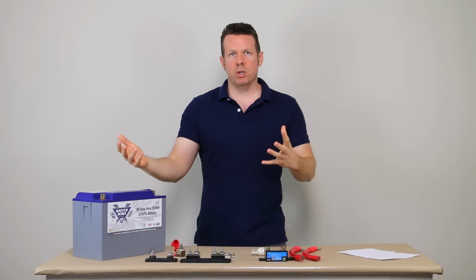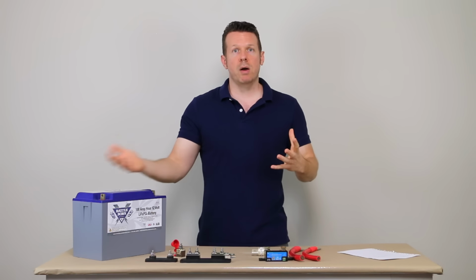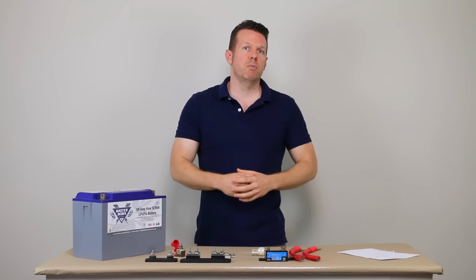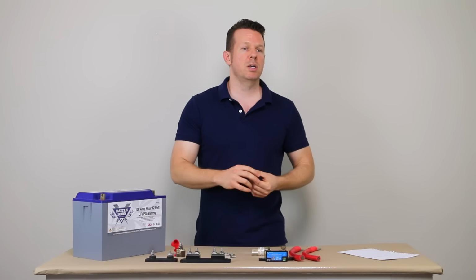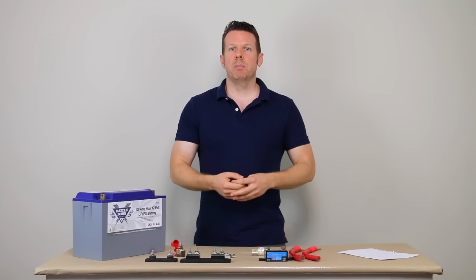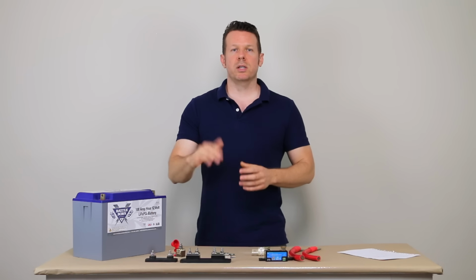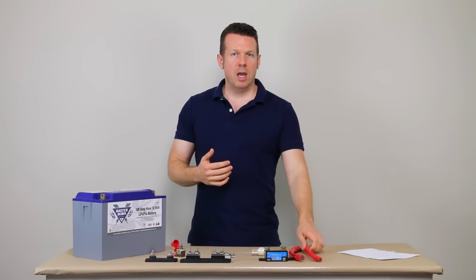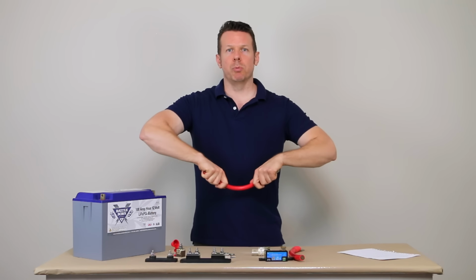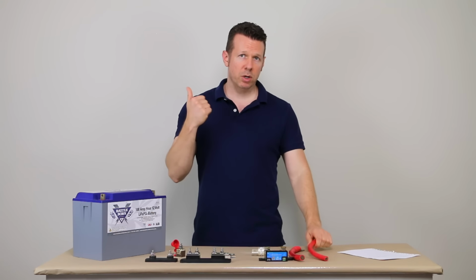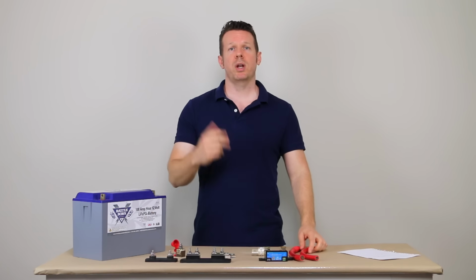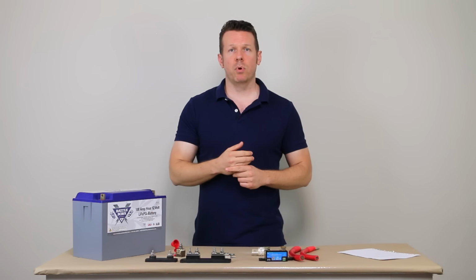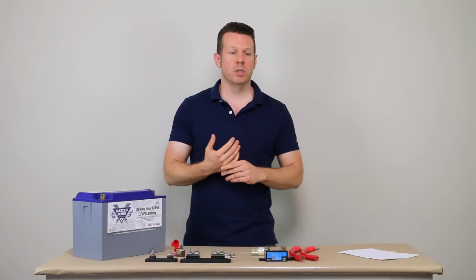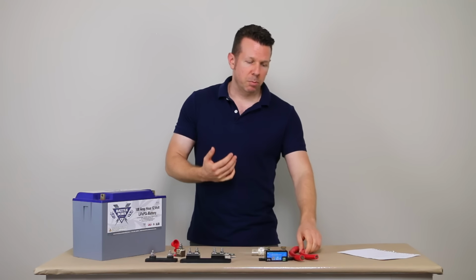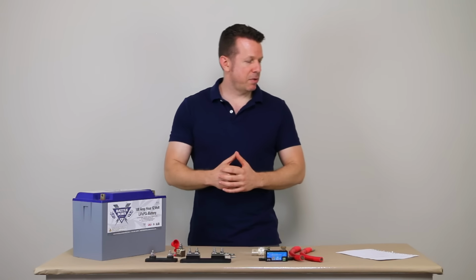In that guy's case, he ended up just omitting the solar, and in off-grid scenarios he relied on the alternator, which is okay. We all pick a strategy, and that was his. But there are other implications not often discussed when you increase battery voltage to use super skinny cables. The converters and solar issues are the two big ones I'd point to with 48 volts. It's less of an issue at 24 volts. That is mistake number 7.